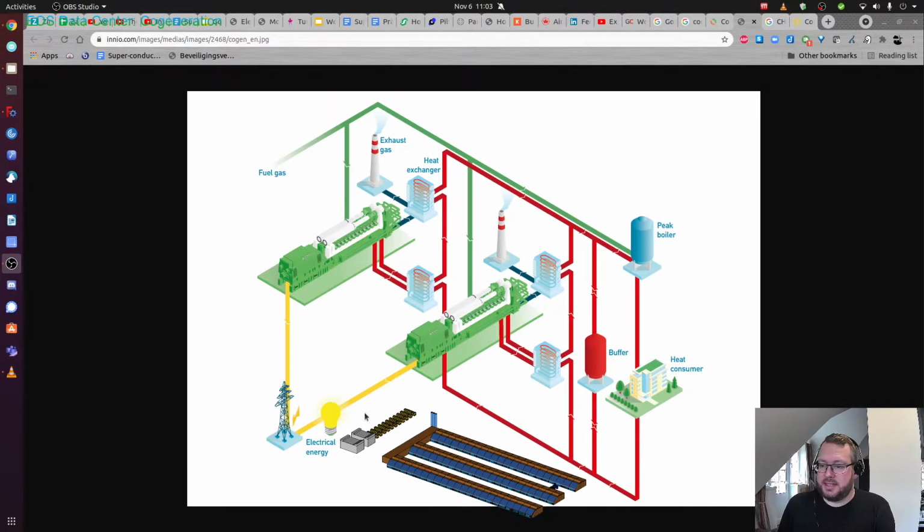And with a sizable data center like this one, where you have a 110 megawatt facility, which is a fairly substantial power plant, you then can go and produce 20 to 80% flexible load for the grid, with very high utilization if you manage. And that's the big if.